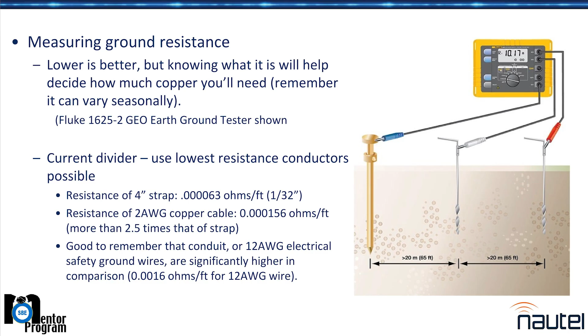I mentioned earlier that ground has a resistance. You can measure it if you're so inclined, but it doesn't matter, because I guarantee whatever the resistance is, it's going to be a whole lot higher than a 4-inch copper strap. There's the relative impedance, or resistance per foot, for 4-inch copper strap versus 2-gauge copper cable: 2.5 times.